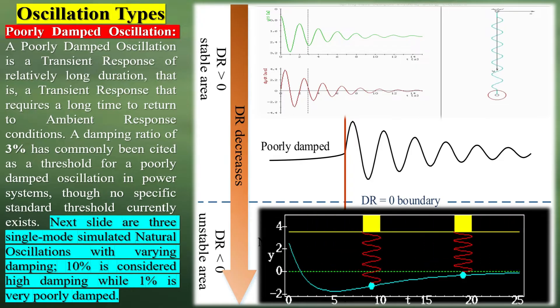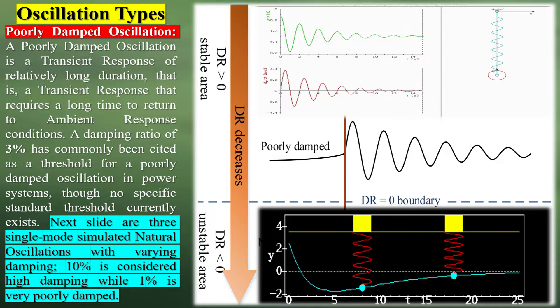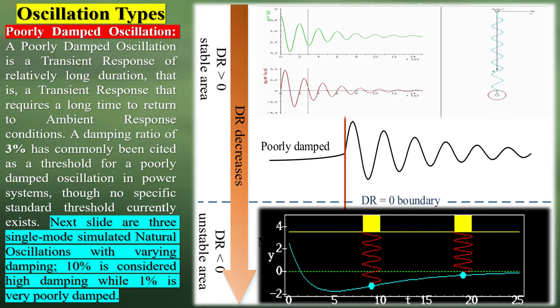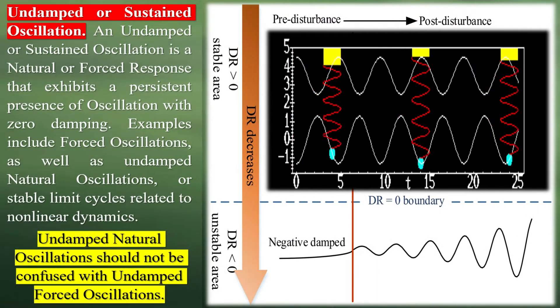Oscillation types by damping. Poorly damped oscillation: a poorly damped oscillation is a transient response of relatively long duration — that is, a transient response that requires a long time to return to ambient response conditions. A damping ratio of 3% has commonly been cited as a threshold for a poorly damped oscillation in power systems, though no specific standard threshold currently exists. 10% is considered high damping, while 1% is very poorly damped.